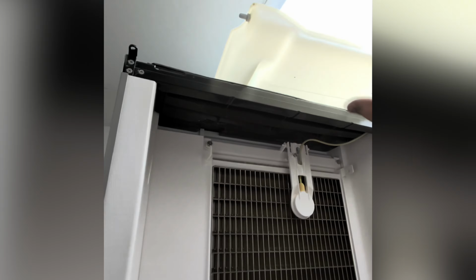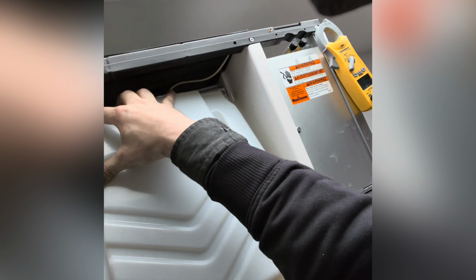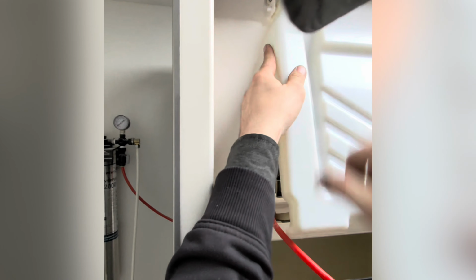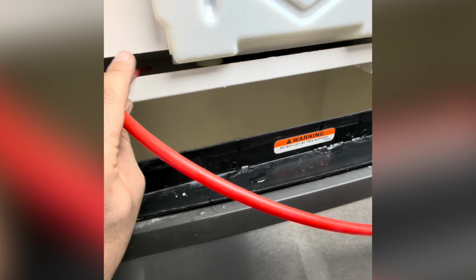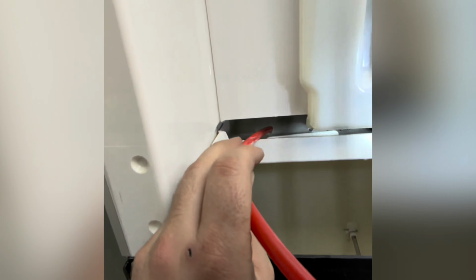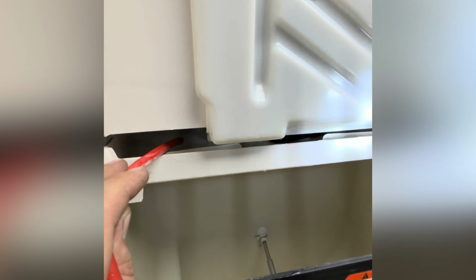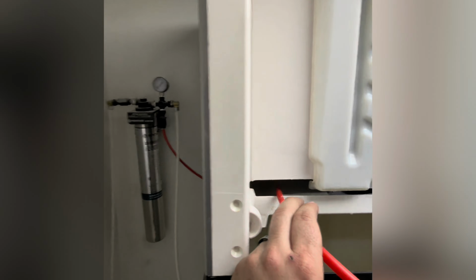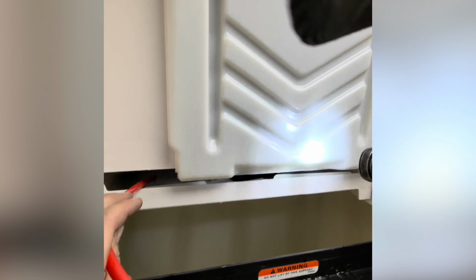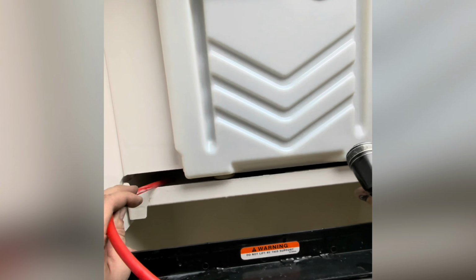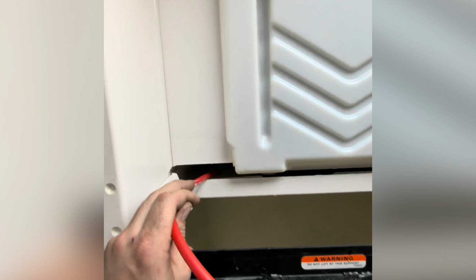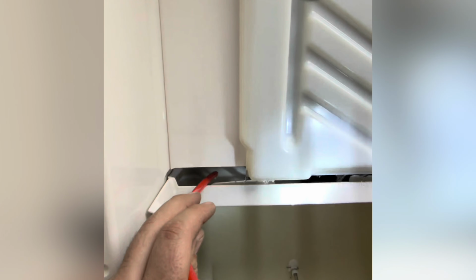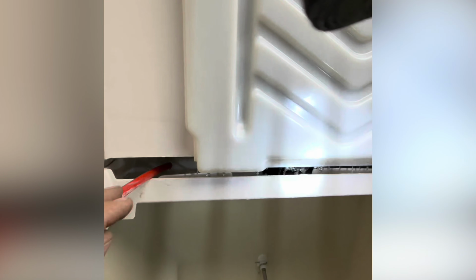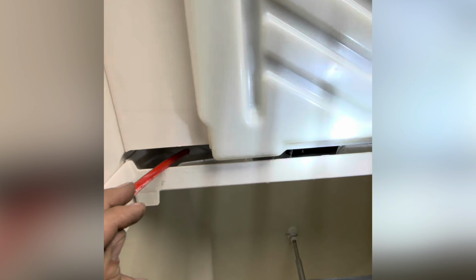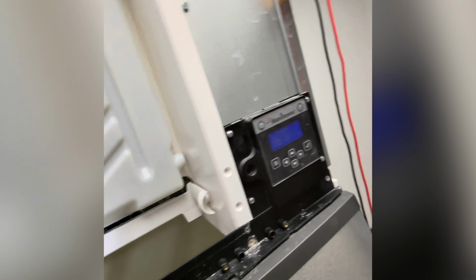It just dropped the ice, so it's definitely good on its refrigeration cycle. It makes ice quite good when there's water in there. What I'm not sure about is why the harvest probe froze to the evaporator coil. It may have been too close. I just made a full turn adjustment because it was way too close to the evap coil. We're gonna run another cycle and see if it goes into harvest and comes out of harvest on its own without any assistance.